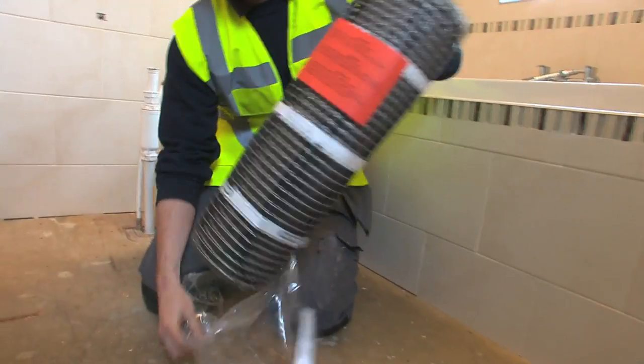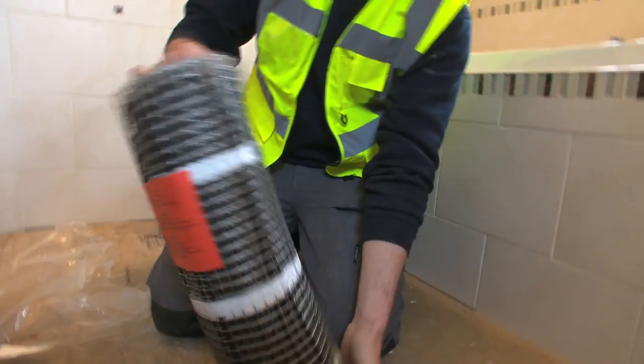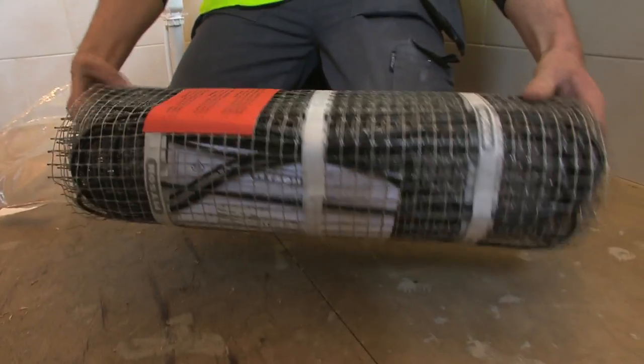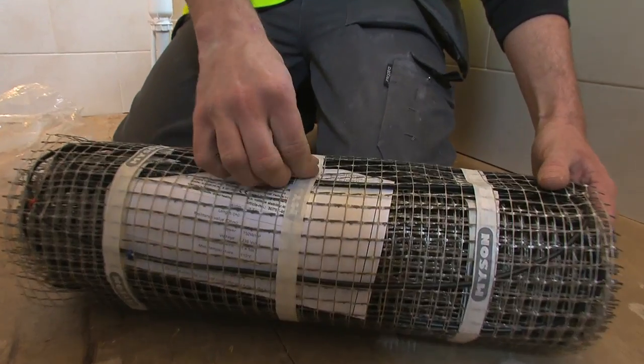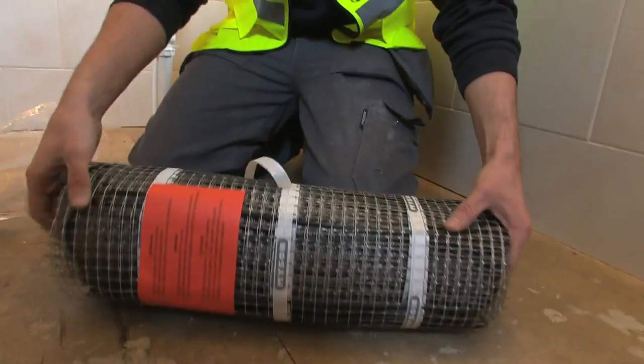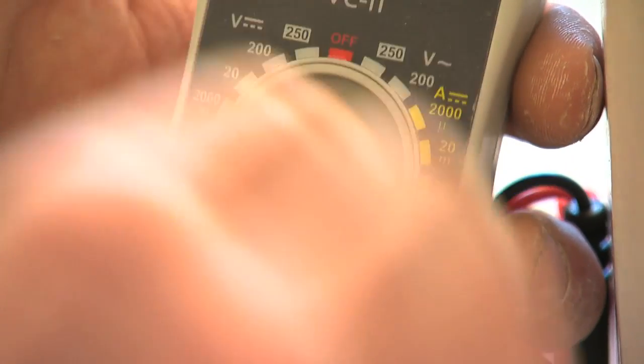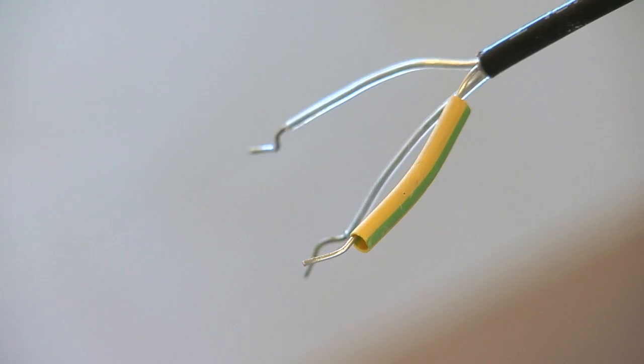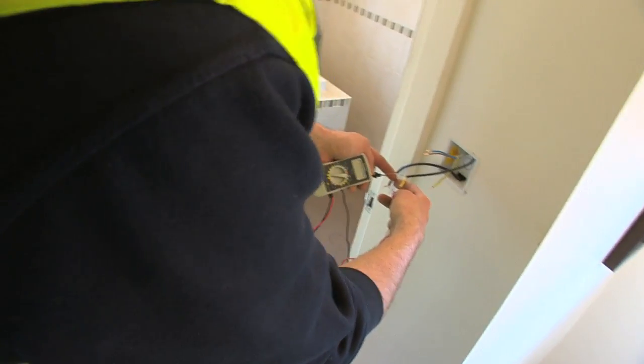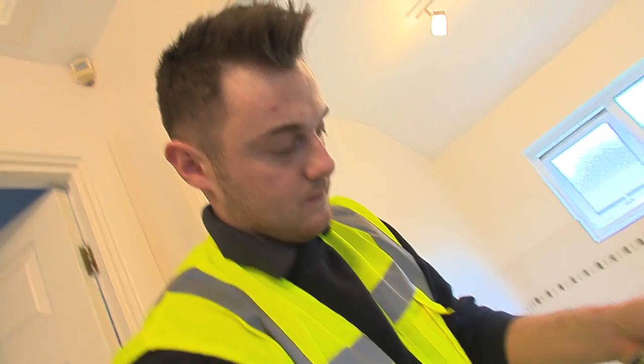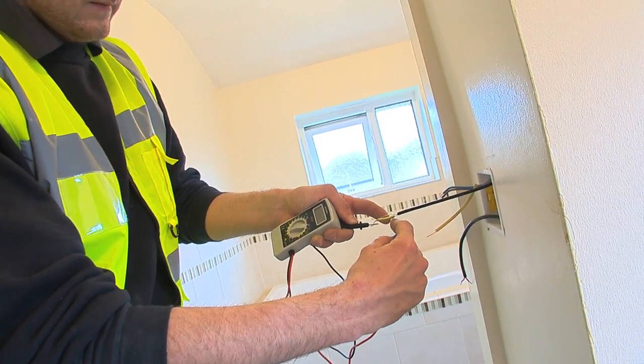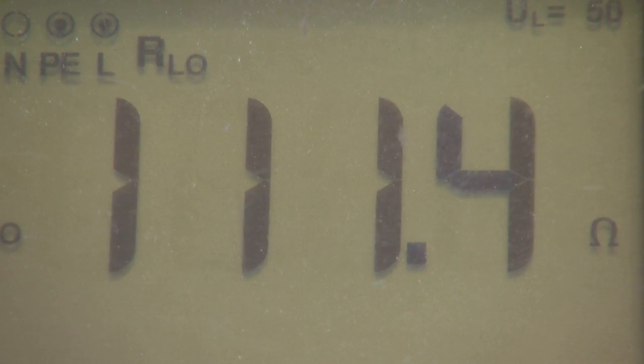Unpack the mat and unravel it. You should test the mat before you start the installation to make sure there are no faults. Any faults should be reported to the supplier immediately. To test the mat, use the multimeter supplied in your box. Connect the wires as shown and turn the knob of the multimeter to ohm 2000. Connect the red and black probes to the connection wires. It's very important that you do not touch the wires when measuring. Check that the readings are correct according to the control card, which is attached to your heating mat. If readings are not within a 5% margin, stop the installation and contact the supplier immediately.